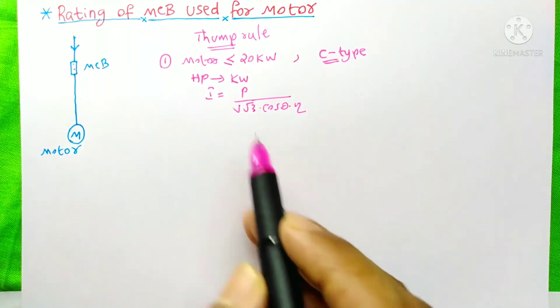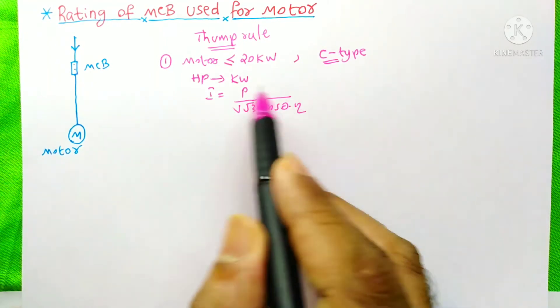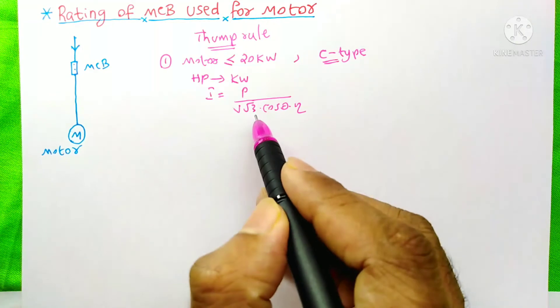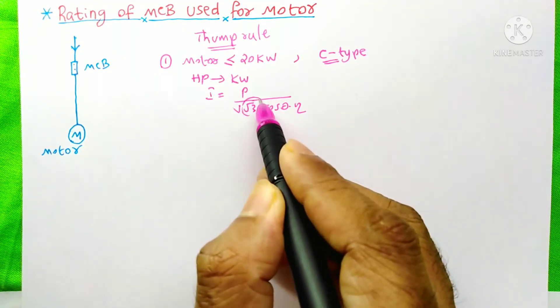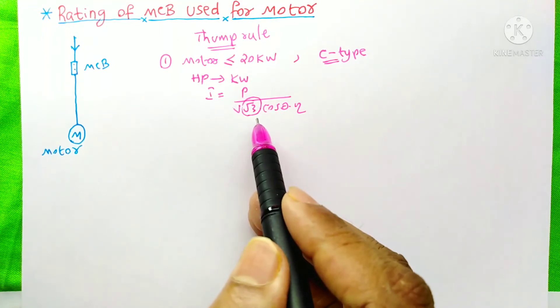To select an MCB, first you need to find the current for the motor. If it is a three-phase motor, then you use this equation. If it is single-phase motor, then you need to avoid this root 3 and find the current and then select a suitable MCB with a C-type.